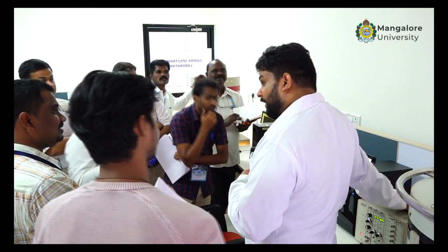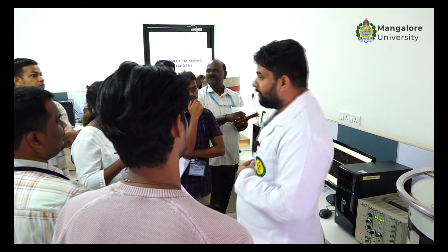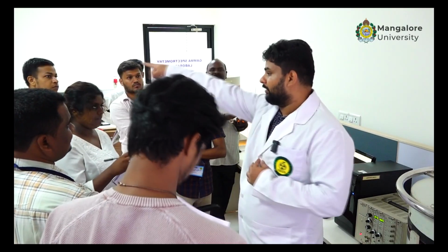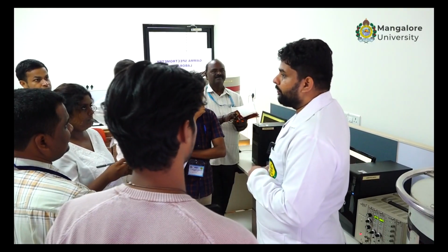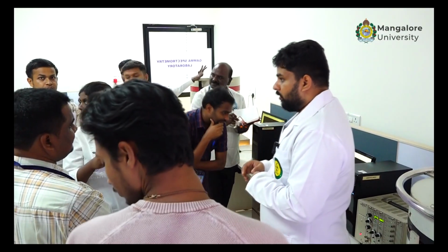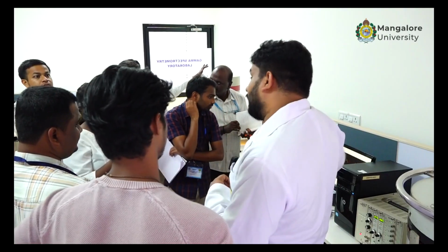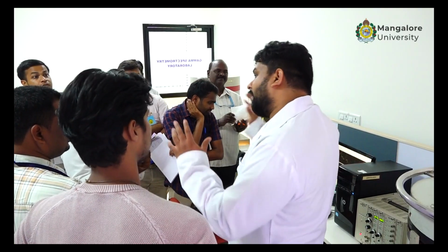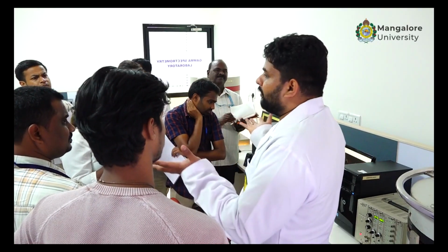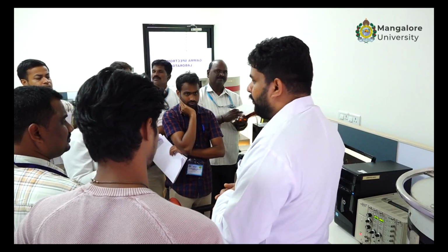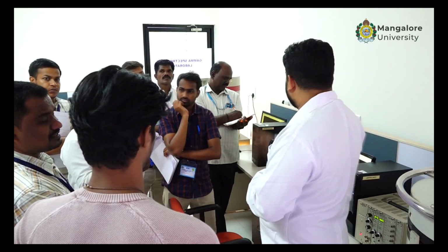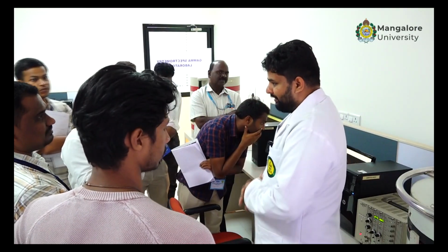This system is 16K, 16,000. That system is 32,000. That is 60,000. But here we have limited it to 1,000. So this 16,000 for sodium iodide we have limited to 1,000 channels because resolution is anyway poor. So it's better to have it at 1,000 channels. But 32K will give you a much better resolution.